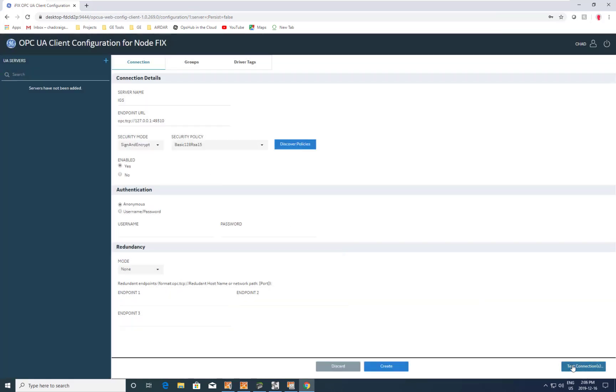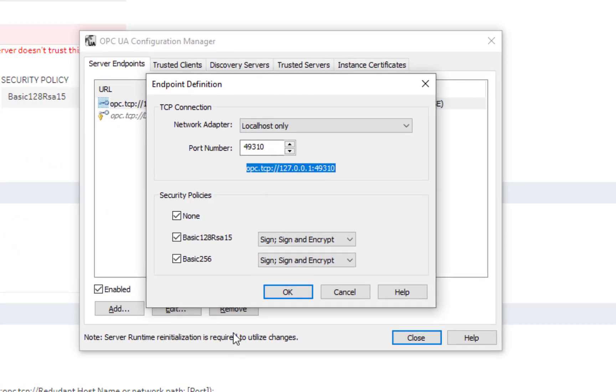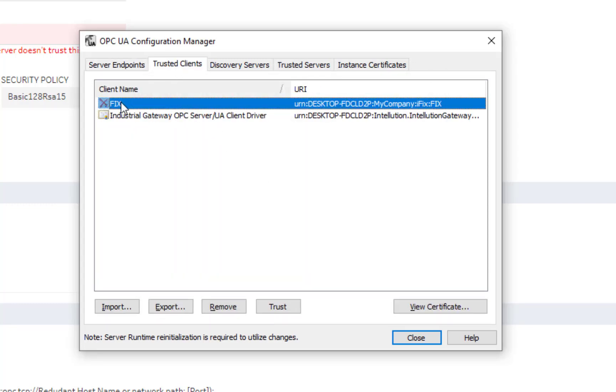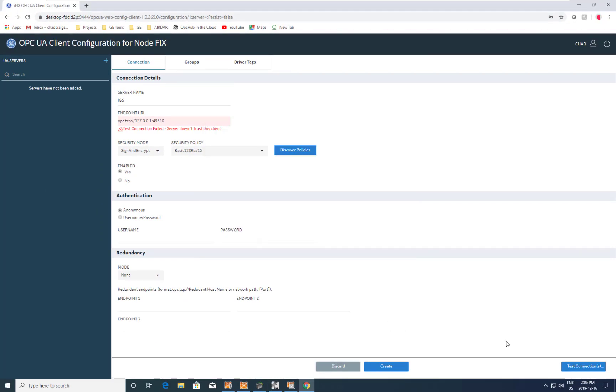If we go ahead and test that connection, we see that right out of the gate the IGS server doesn't trust this client. So we need to go back into the IGS configuration, go to the trusted clients list, and we'll see that iFix is in there as untrusted. Let's trust that, go back, and hit test connection again.